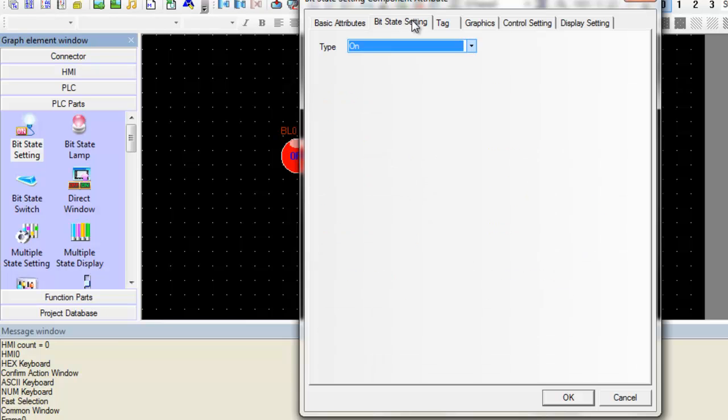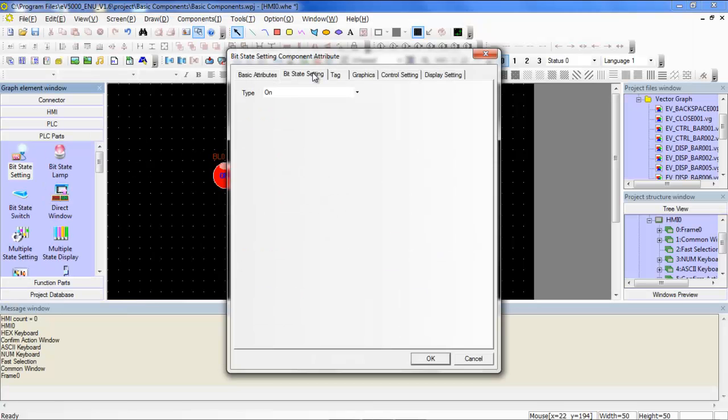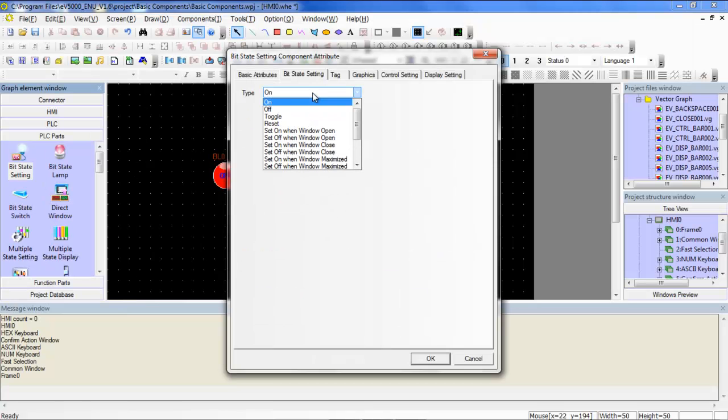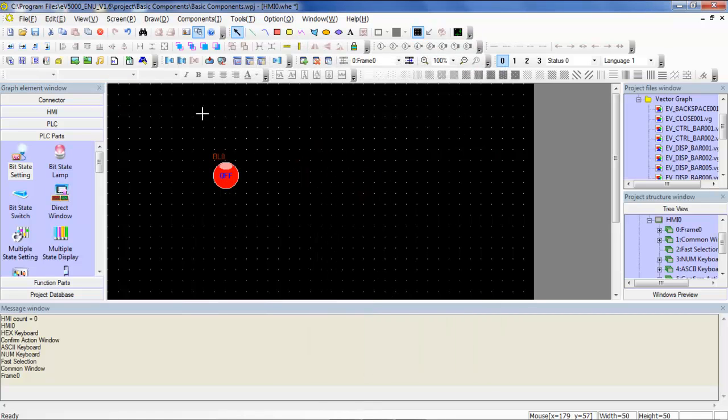Next, let's go over to the bit state setting tab and select toggle as our type. Every time the bit state setting component is pressed, the corresponding PLC bit register will be flipped from its current status. So if it's on, it will go to off. If it's off, it will go to on.